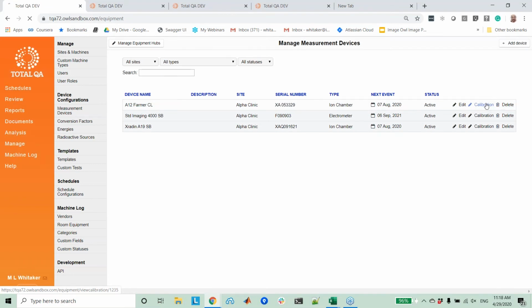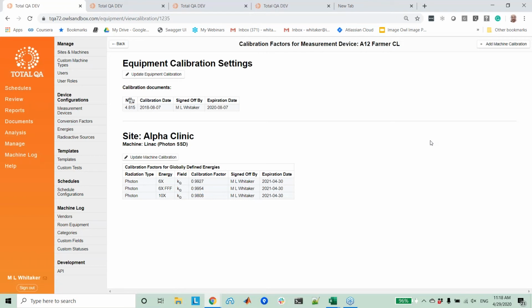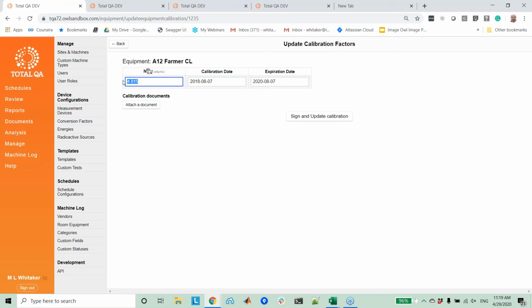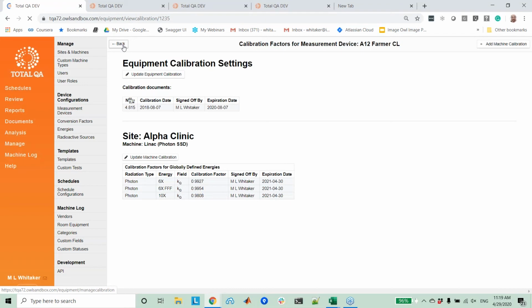But what you also need to do then is add the calibrations for that. There are two parts to that. In the case of an ion chamber, you're going to do the actual equipment calibration. This is entering the factor in centigray per nanocoulomb, which you get from the calibration lab, with the calibration date. In this case, you would definitely want to put in an expiration date. You could attach a document, so you could attach your actual calibration documents that you got from the lab. So again, they're all kept in one place. Sign off and calibrate that.